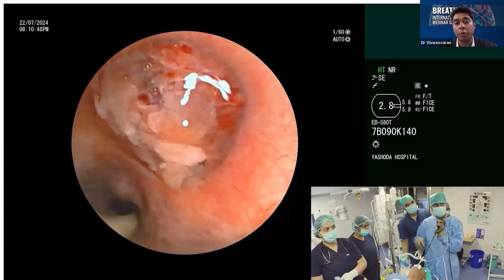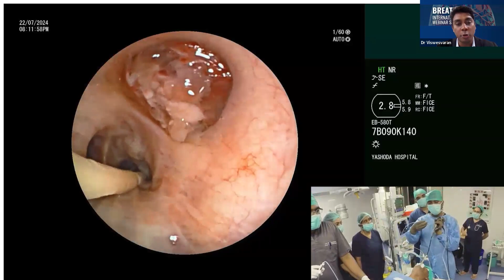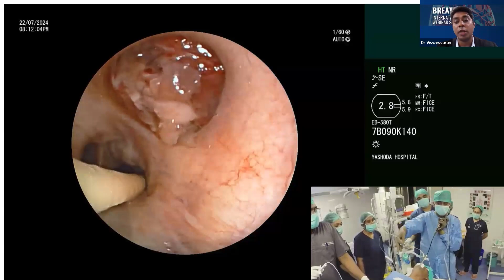The important point to note while doing an electrosurgical snaring is that the FiO2 requirement should be kept less than 0.4. Anything above 0.4 can make you prone to airway fire. So I make sure that I give a proper instruction and I set the watts in the electrosurgical unit around 20 to 25. And once I am very sure that the anesthetist has kept the FiO2 less than 0.4 and the settings are perfectly made and my snare is checked, now I will be going for an electrosurgical snaring of the tumor.